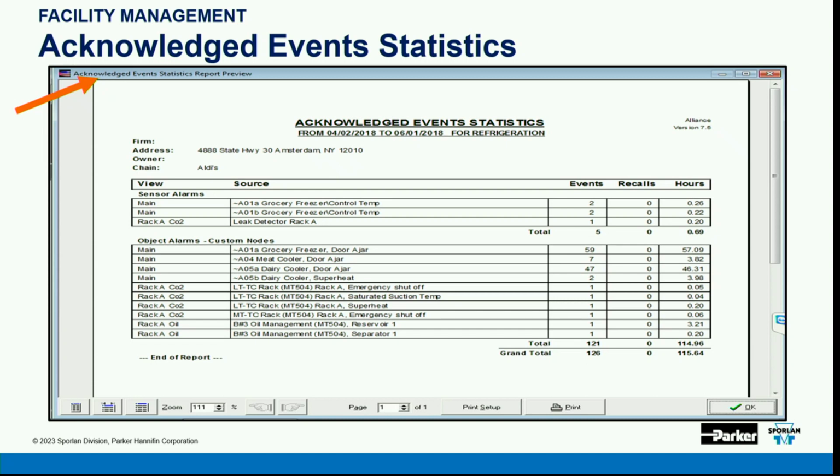It'll tell you. If you guessed wrong and your base value is off for one of the coolers, it's going to warn you: base value needs to be readjusted. You get to the case, you pull the graph, I'll talk about that later, and you'll say, ooh, I made a mistake. I set the base value at 20%, it really should be at 32%, okay? Microthermo was smart enough to let you know that, okay?